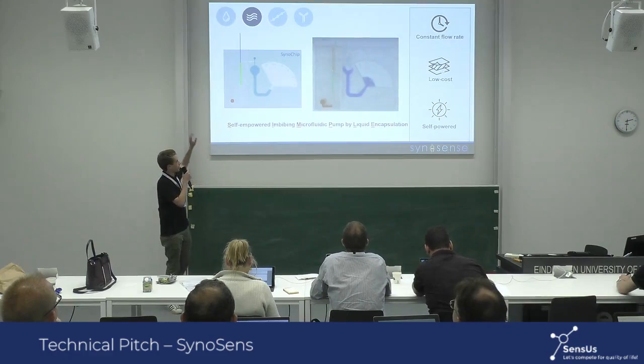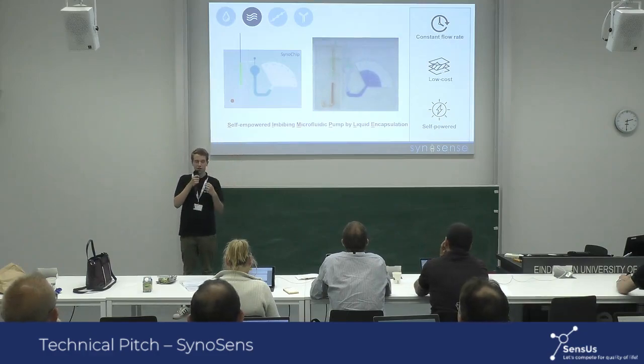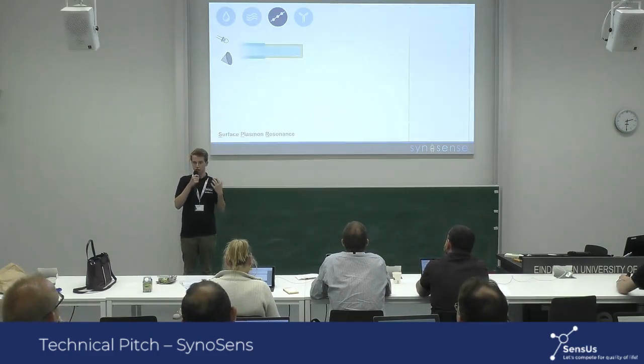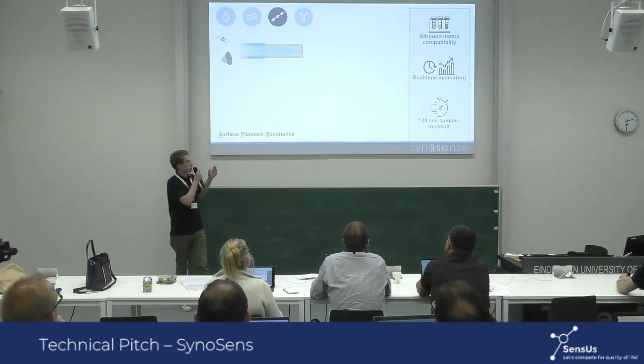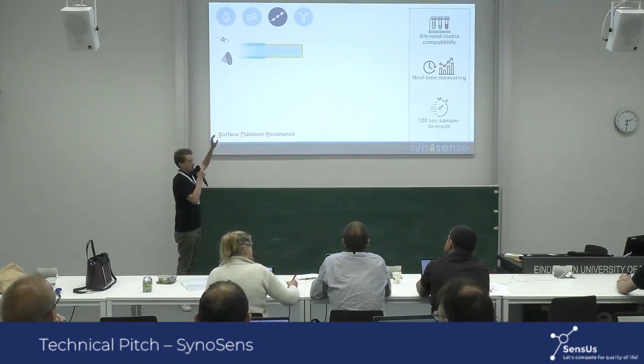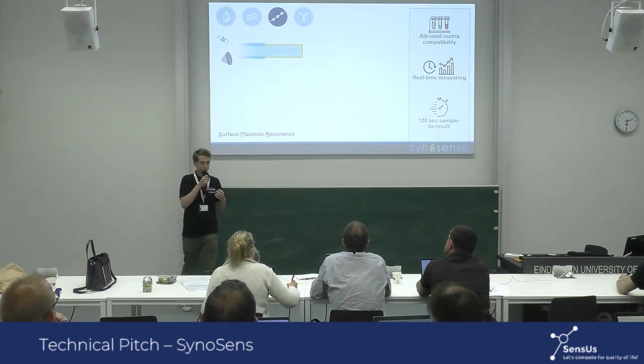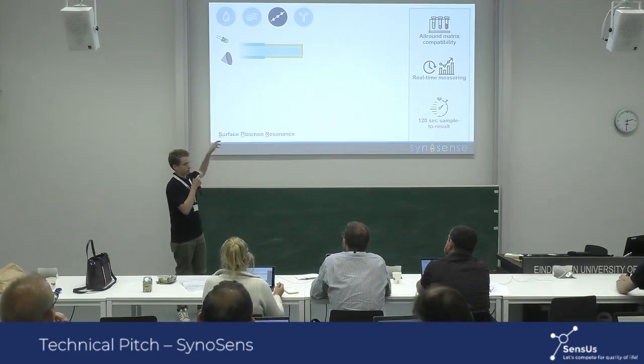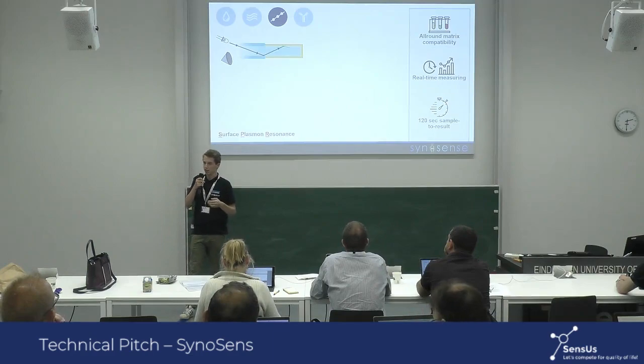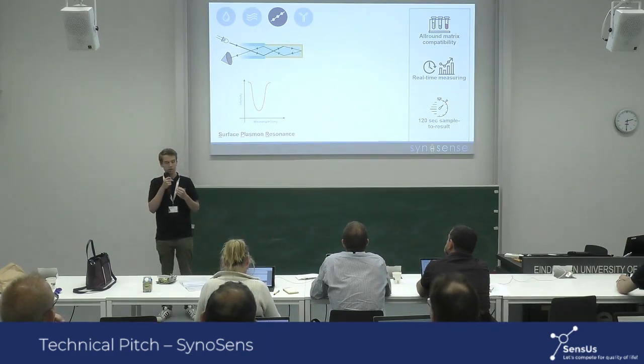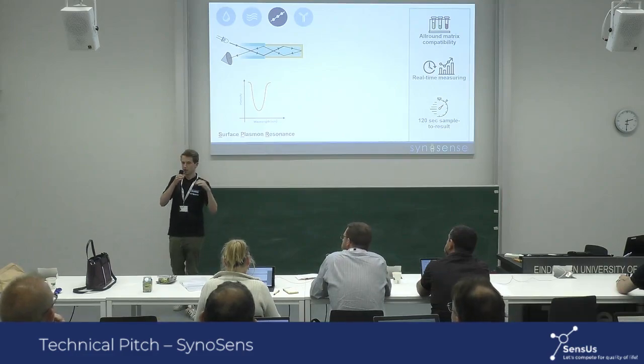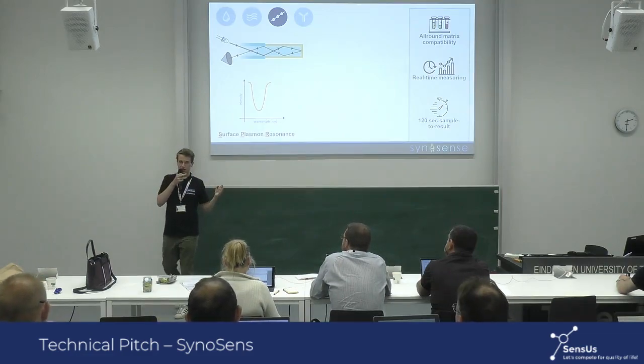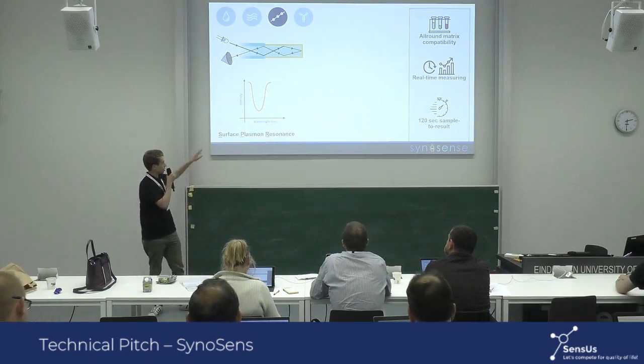Now, after the blood has been brought to the probe, the sample is measured by SPR, or surface plasmon resonance. Our probe consists of an optical fiber that has been stripped and coated with gold at its end. When light is sent through the fiber, it will be internally reflected and eventually cause the creation of surface plasmons. The resonance of these surface plasmons with the incident light will cause a decrease in the intensity of the reflected light, which you can see here.